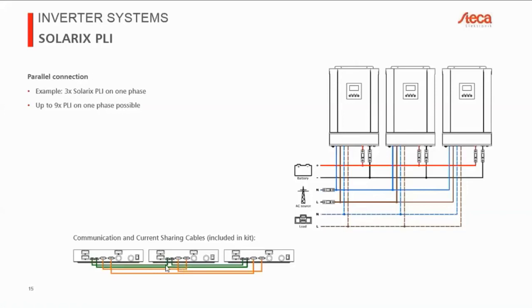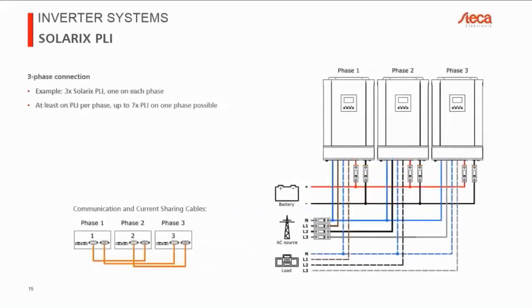So this was an example of a single phase system with 3 inverters, 3 SOLARIX PLI. Now we have exactly the same thing except in a 3-phase system. So again, we're connecting all the inverters on the same battery. This is again a requirement. We connect the neutral, obviously the same neutral for each inverter, and then we connect phase 1, 2, and 3 to the various inverters. And on the load output, we do the same. We distribute that as a 3-phase system.